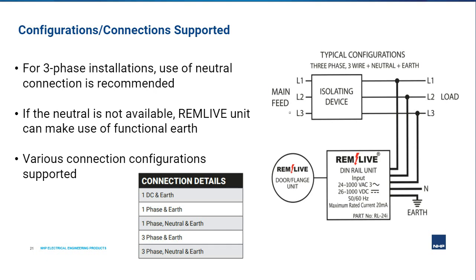For three-phase 4-wire systems, the neutral on the base unit is connected to the neutral conductor. And if you're using a three-phase 3-wire system, that's with no neutral conductor, the neutral on the REMLIVE base unit can be connected to functional earth. The use of a neutral conductor or earth connection is strongly recommended for the use of the REMLIVE liveline indicator.